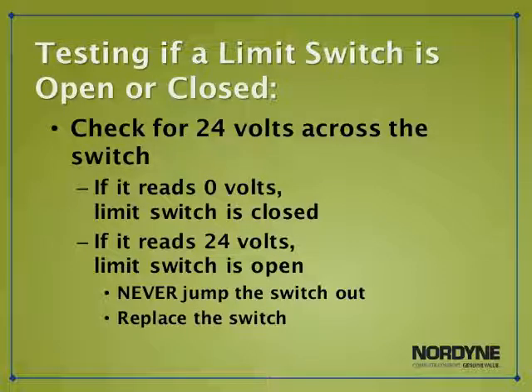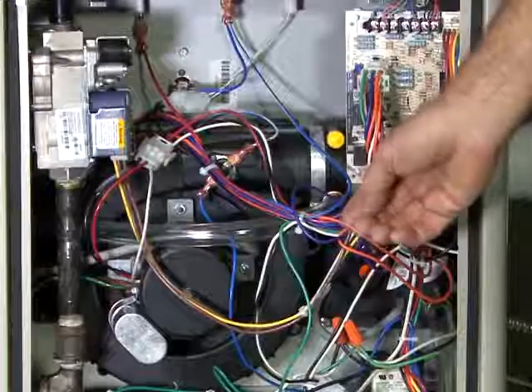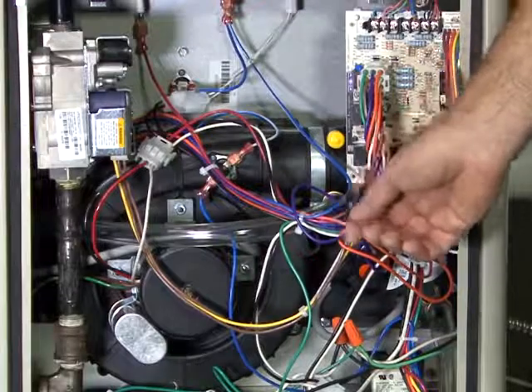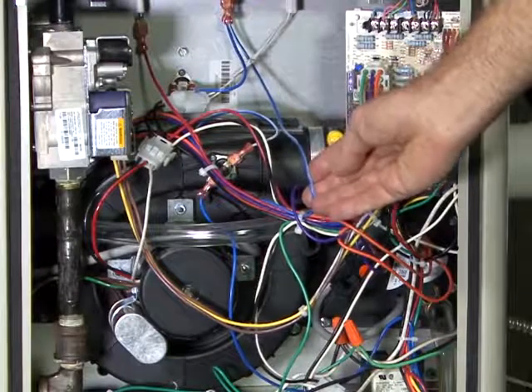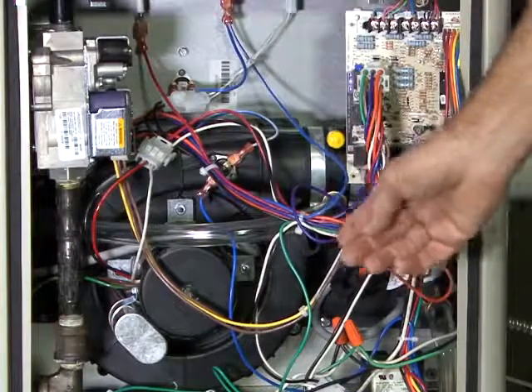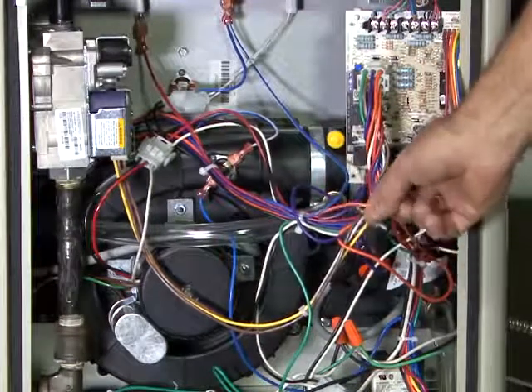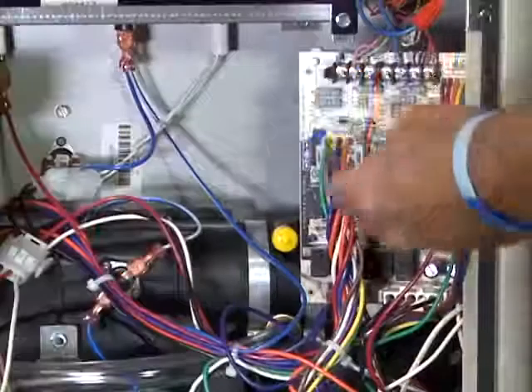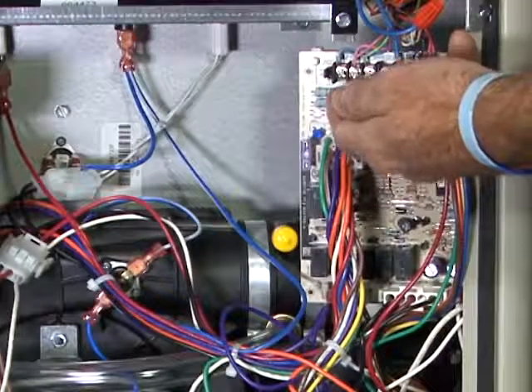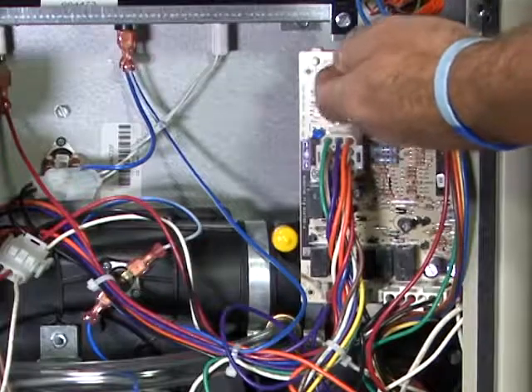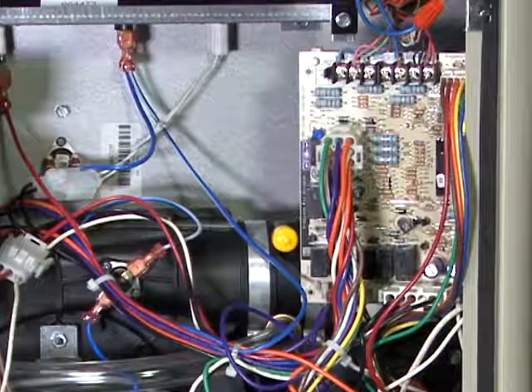After you replace the switch, make sure to start the furnace up and test it to see if it's operating within the temperature limits. When troubleshooting any of the limit circuit, pressure switch circuit, or control wiring circuit, don't get too wrapped up in all the wires within your furnace. Just focus on the circuit that is giving you the problems. If it's a limit circuit, it's going to be the blue wire. If it's your pressure switch, it's either going to be the purple wire or the orange wire. And if it's your control wiring, it's going to be attached at your control board at the terminal strips going to your thermostat. By doing this, we'll help you to quickly troubleshoot the furnace and prevent future callbacks on this equipment.